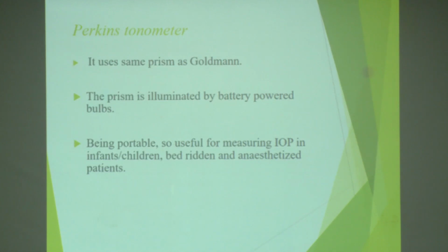This is about the Perkins tonometer. It is based on the same principle as that of Goldmann, and being portable, it is useful in measuring IOP in infants, children, bedridden, and sedated patients.